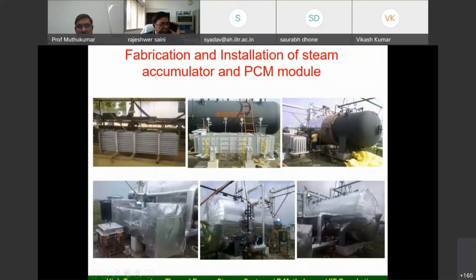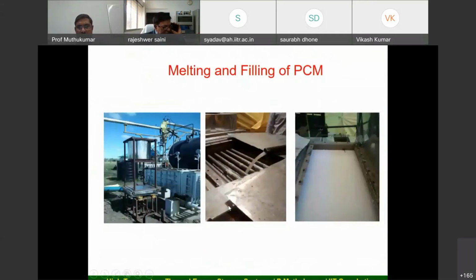That's how this is insulated. And because we need to completely make the PCM in the form of liquid, we charge them carefully. Then before putting the system into operation, this was tested hydrostatically at about 90 bar pressure for about 48 hours. Only after that was this allowed to be tested.